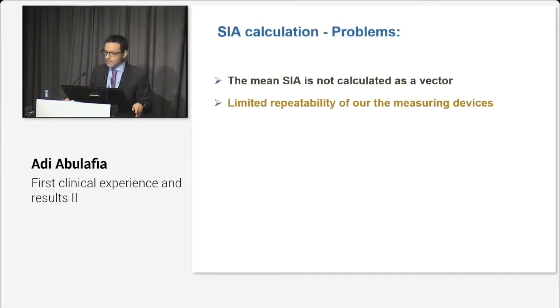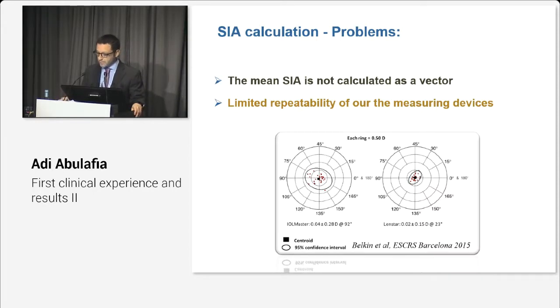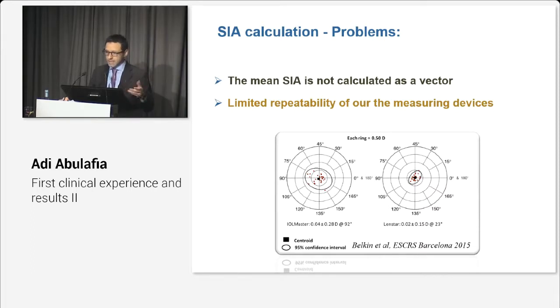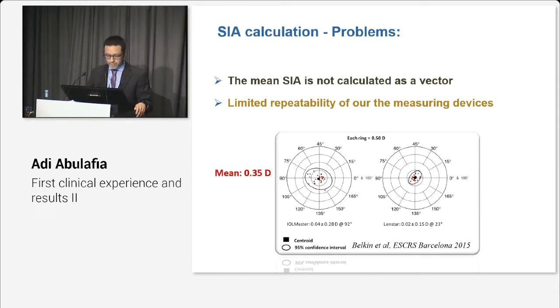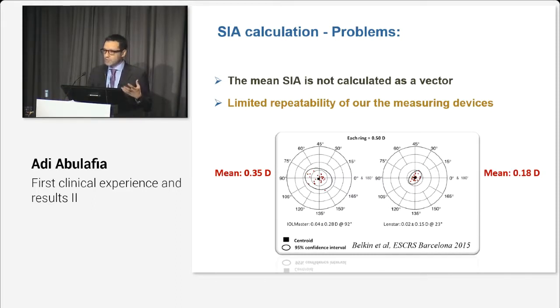Another issue is the limited repeatability of our measuring devices. Looking again at the double-angle plots of corneal astigmatism differences in healthy volunteers measured one week apart — let's do a theoretical exercise and calculate the mean SIA the traditional way. We get a pseudo-SIA, which should be zero because we didn't even touch these corneas. For the IOL Master, we get a pseudo-SIA of 0.35 diopters, and for the LENSTAR, 0.18 diopters — an SIA without touching the cornea, resulting from measurement noise. However, if we use the centroid values, the SIA is zero as it should be.